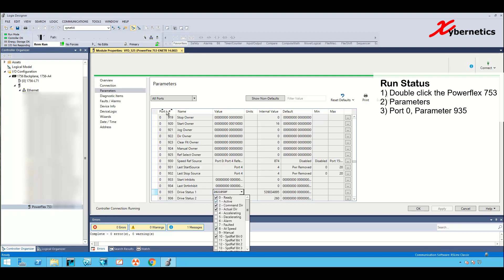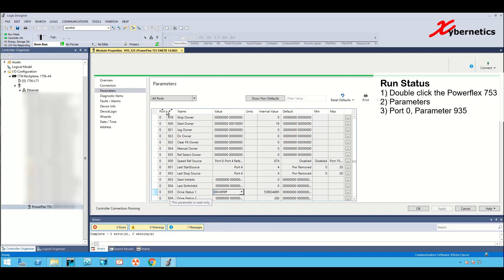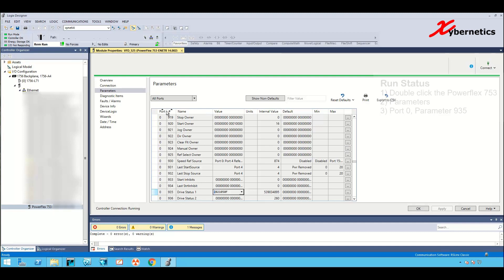If you see this being checked, which means that the VFD is running and active, this has to be disabled. One thing to note is that this line here, parameter 935, is read-only, right? So you can't really change it from here. You're gonna have to stop your drive using some other means.